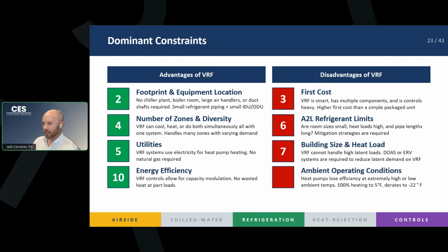And conversely, looking at some of the disadvantages of VRF, first cost, right? This is going to come down to what you're comparing it to ultimately, but VRF has a lot of controls. It has multiple components, right? And those are going to add up in cost. While they're small components, you're going to have more of them. So maybe versus a rooftop unit where it's only one packaged piece of equipment, you're going to be a little bit more expensive, but you're not going to get the same performance or the diversity or the zones, right? So it's a trade-off. In terms of first cost, it is a little bit pricier than a packaged rooftop unit, but if you're comparing it to a chiller plant, we're nowhere near as expensive. So it is a disadvantage when you're trying to keep things simple, but if you're trying to compare it to a huge chiller plant, you're going to win, right? So that's a disadvantage, but it depends.